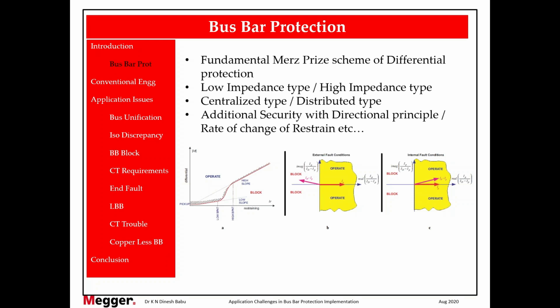So whatever we are going to discuss today is to handle worst case scenarios only, because most of the time you might feel that our bus bar is in service for the past 10 years, no issues, but that's because we are talking about 99% of the cases. But normally power system protection is designed for worst case scenarios. So even if your settings are not accurate, maybe somebody said 19%, somebody said 21%, that means there is a mismatch. Even if the setting is wrong, the relay should be intelligent enough to differentiate between a healthy condition and a fault condition. That's the power system protection principle: do not trip during healthy condition, trip only during fault condition.